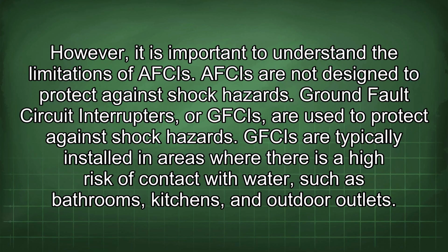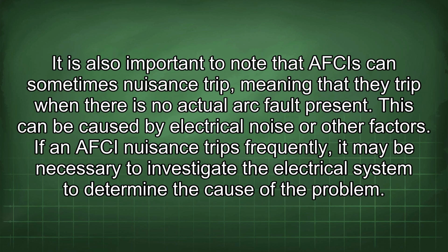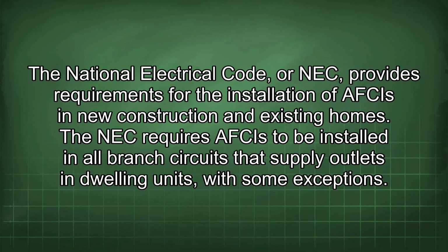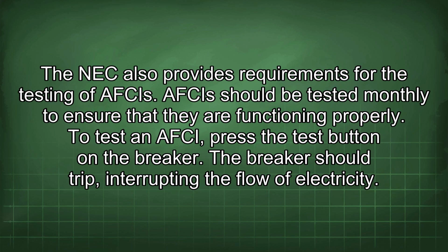and outdoor outlets. It is also important to note that AFCIs can sometimes nuisance trip, meaning that they trip when there is no actual arc fault present. This can be caused by electrical noise or other factors. If an AFCI nuisance trips frequently, it may be necessary to investigate the electrical system to determine the cause of the problem. The National Electrical Code, or NEC, provides requirements for the installation of AFCIs in new construction and existing homes. The NEC requires AFCIs to be installed in all branch circuits that supply outlets in dwelling units, with some exceptions. The NEC also provides requirements for the testing of AFCIs.